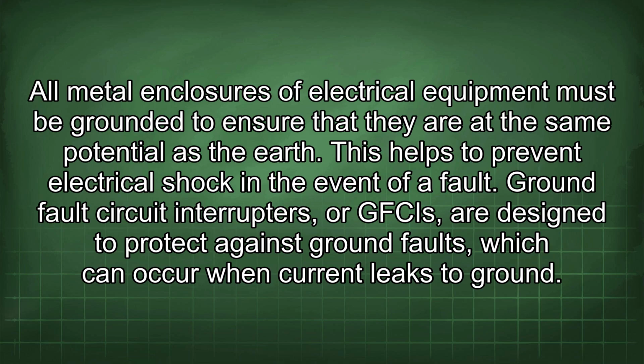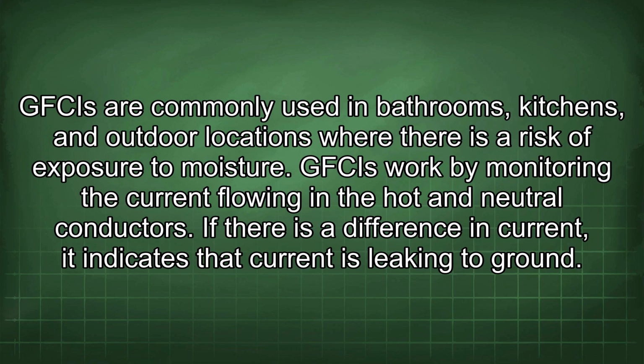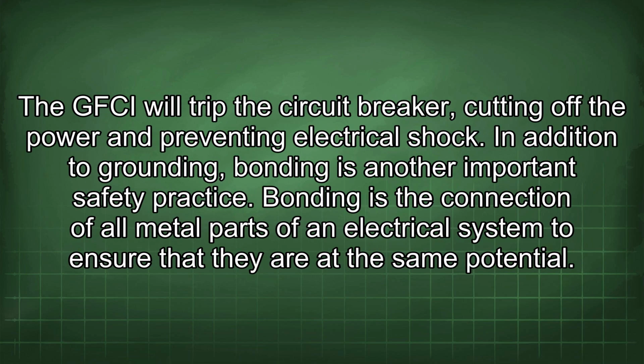Ground fault circuit interrupters, or GFCIs, are designed to protect against ground faults, which can occur when current leaks to ground. GFCIs are commonly used in bathrooms, kitchens, and outdoor locations where there is a risk of exposure to moisture. GFCIs work by monitoring the current flowing in the hot and neutral conductors. If there is a difference in current, it indicates that current is leaking to ground. The GFCI will trip the circuit breaker, cutting off the power and preventing electrical shock.